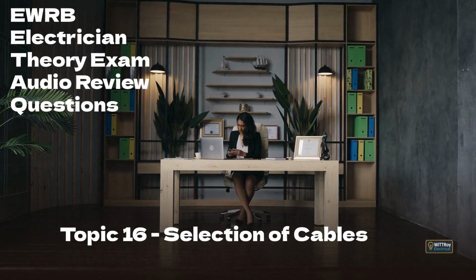Pause. 5, 4, 3, 2, 1, 0. Correct answer is option A. Soil can act as insulation depending on type and moisture. If heat cannot escape, conductor temperature rises, so the allowable current may be lower and derating may apply.